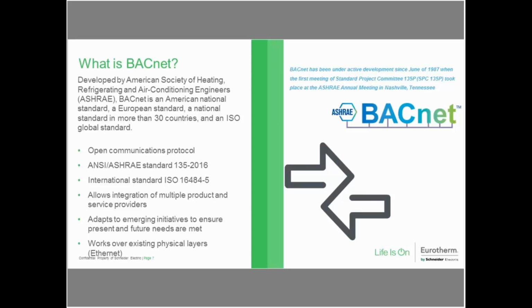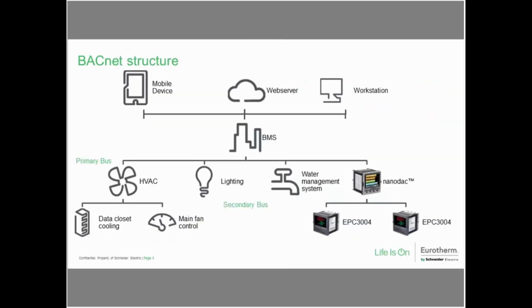They're more so, I suppose, geared towards commercial applications, but as we move forward, the industrial, commercial, and consumer applications are starting, those lines are starting to become more blurred as things and devices become more connected. So the good thing about BACnet is that it works over existing physical layers. So what's a physical layer? Ethernet, your typical serial copper wire comms, there's some wireless communications, and so essentially that's the physical protocol layer of communications, but BACnet slides right on top.